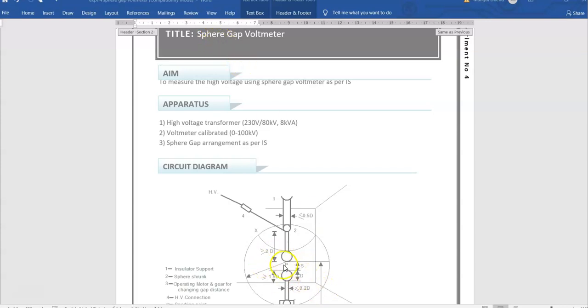You use this sphere gap for air testing. Air is there between the two spheres. You apply the voltage and go on increasing it. If you go on increasing the voltage, air breakdown occurs, and you can find out the breakdown voltage for a certain gap distance, and then find out the breakdown strength. So this is the experiment, but here the objective is different. Objective is sphere gap voltmeter, meaning how we can use the sphere gap for measurement of unknown voltage.